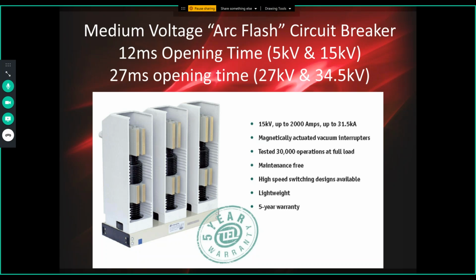But the key point here is, up through 15 kV, either 5 kV or 15 kV applications, that key 12 millisecond opening time. And you combine that with 30,000 operations at full load, again, orders of magnitude more reliable mechanically than any other circuit breaker on the market.